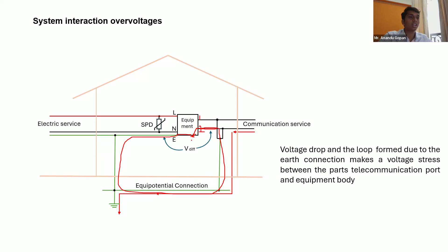When you're going to follow a mesh bonding system, I will list out its requirements. If you're going to follow a mesh bonding system, the DC resistance of this grid to adjacent points must be less than 1 milliohm. It's a very demanding requirement.